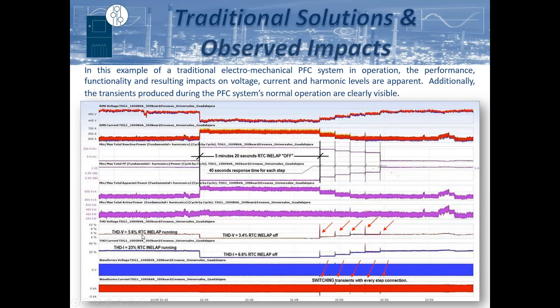But also, if the system isn't tuned properly or designed to fit the network conditions that are present, you can have some negative impacts on harmonics. So you can see here that their total harmonic distortion for voltage when the system is engaged is about 5.6%, which is fairly significant, whereas when it's disengaged, that's reduced to 3.4%. And every single time these groups are brought in, you see these spikes in the harmonic distortion, and you can also see the transients being induced.